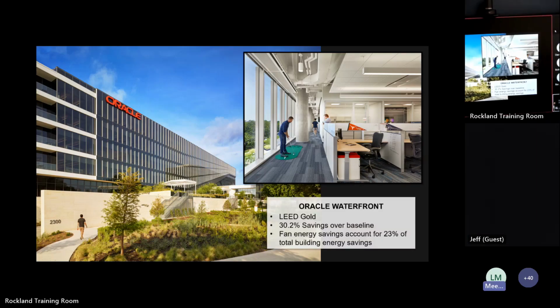Okay, so getting into the different types of applications. You saw this, or part of this, project earlier with the guy playing putt putt, and I don't know who has time for that. But Oracle was able to attain LEED Gold, with 30% energy savings over the ASHRAE baseline. 23% of that 30% was fan energy, so the majority of the energy savings was from fan energy, reducing that horsepower. That lines up with what we were talking about earlier on the benefits.